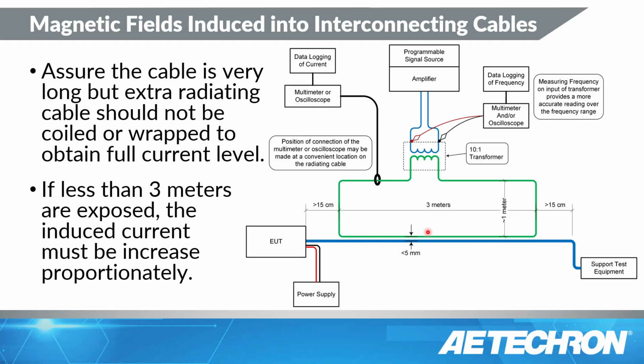If you do have a shorter cable and you're capable of having this transformer somewhat close to your test equipment, you're going to end up with a lot of extra cable. Do not wrap it. Once again, that coil of wire is going to be a pretty high impedance, especially when we start dealing with category W, where you have to get up to 32 kilohertz to perform this test. Getting that far high in frequency, that much current, can be a challenge if you have a coil of wire here. So keep that wire straight. If you need to serpentine it or something of that nature, that's fine. But I just recommend leaving it straight, letting it hang on the floor, whatever. Just do not coil it up.